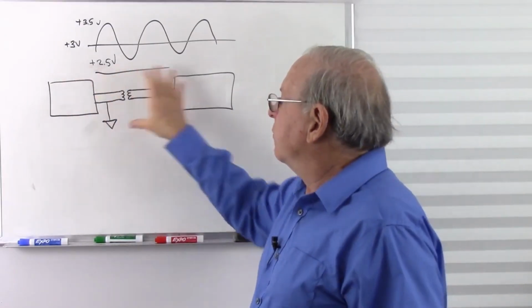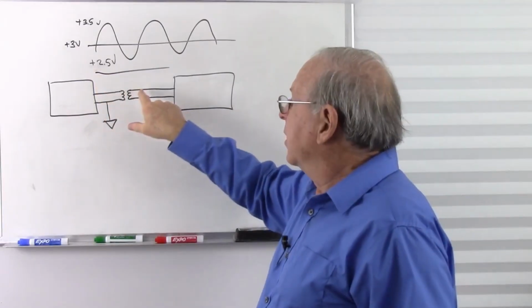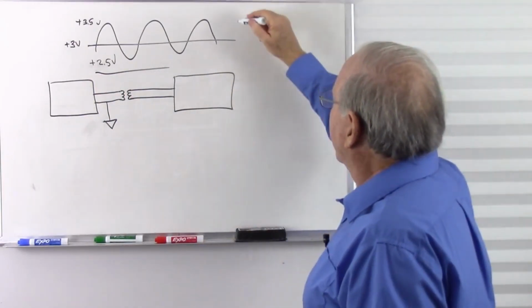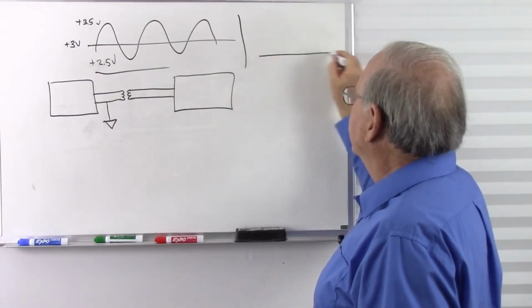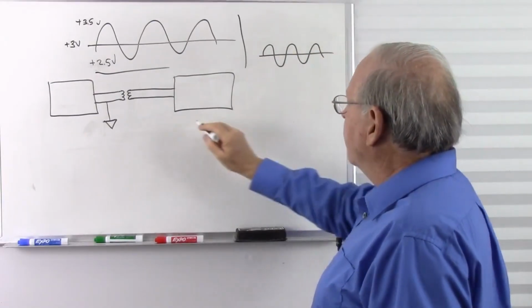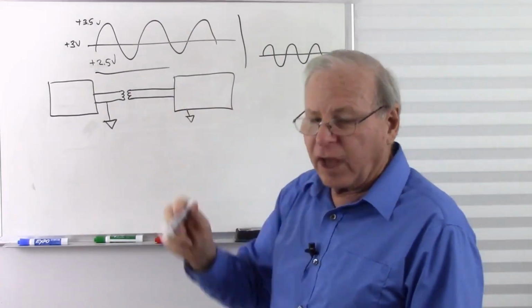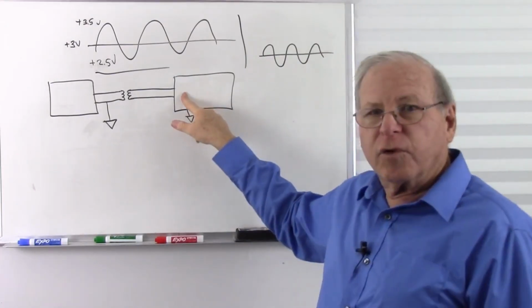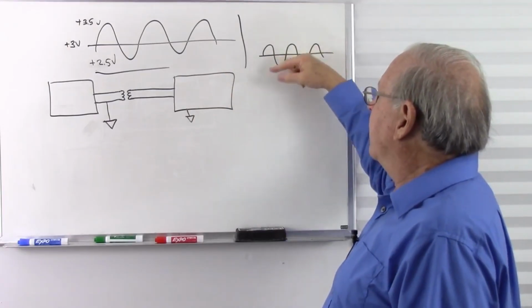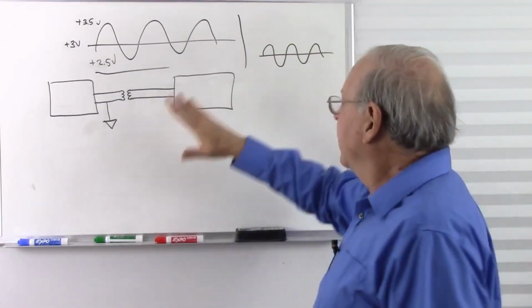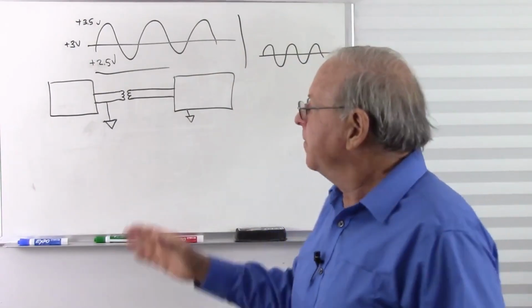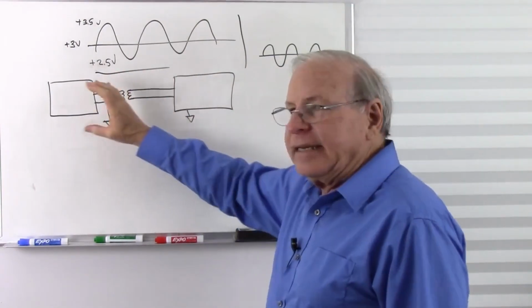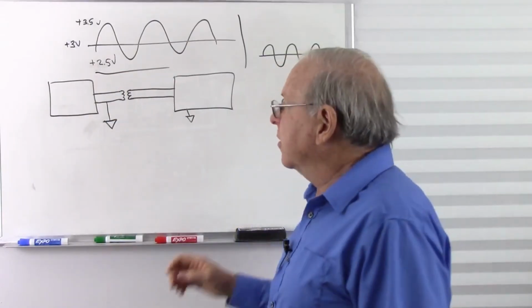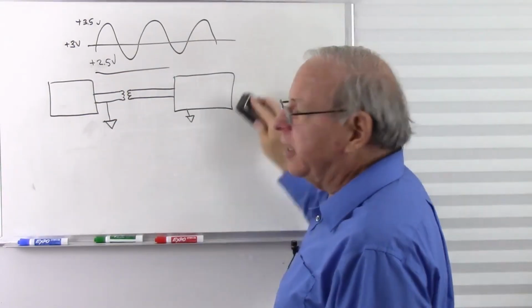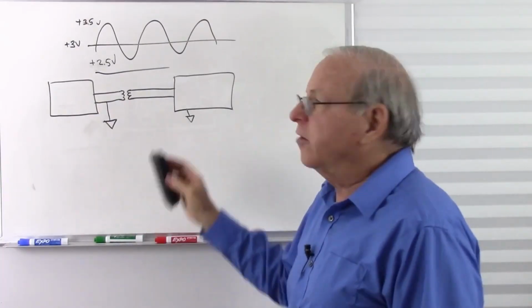So the same thing happens here. That mismatch in voltages, the 3 volts, doesn't get through. All that gets through is on the other side. Once I go through the transformer, I'm centered on 0 volts because that's according to this side. I'm measuring according to a 0 volt reference over here. I see the voltage going up and down by 1/2 volt up and 1/2 volt down, and that's working just like I expect. So that will block any DC from getting from one side to the other. So that's another use for an isolation transformer, basically a DC block in this particular case.